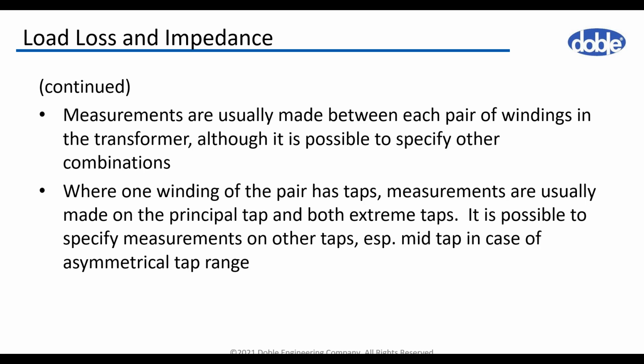In case the unit has more than 2 windings, the load loss measurement is performed between each pair of the windings. In case of a 3 windings transformer, we have 3 combinations. The results are then recalculated to allocate impedance and losses to individual windings. In a transformer with tapped windings exceeding variation of 5%, the test is performed on the principal and both extreme tap positions. This is important for parallel operation of the transformer. Measurement at different tap positions could be specified in the inquiry, and especially in case of an asymmetrical tap range, the measurement of losses could be done on the middle tap position.